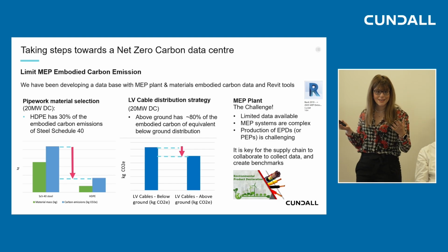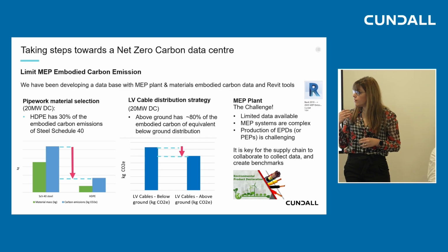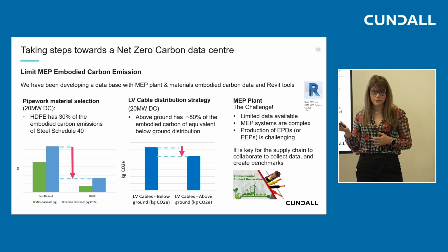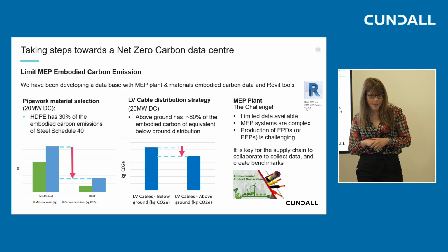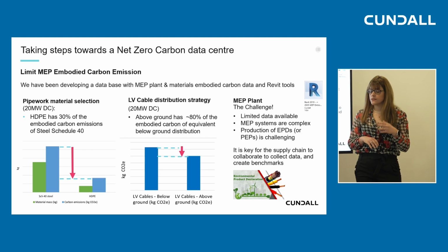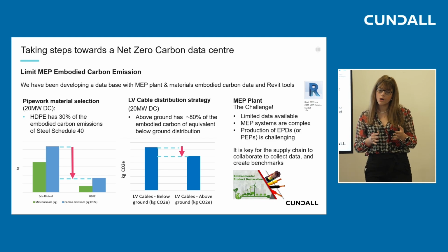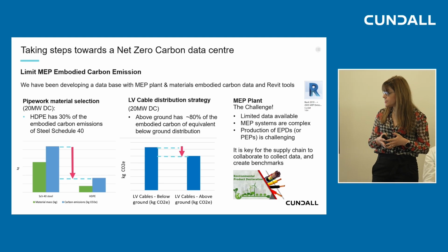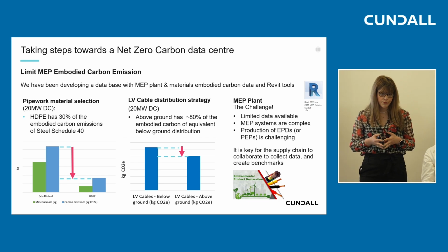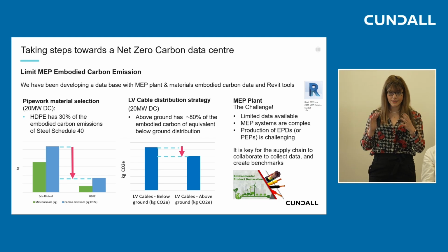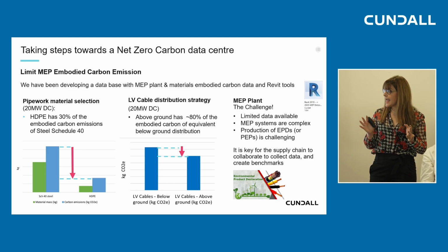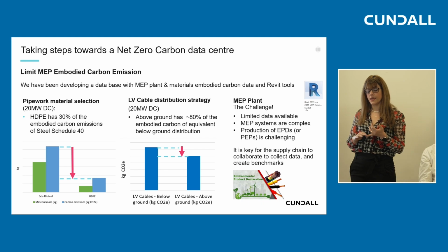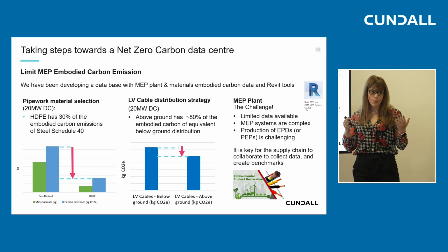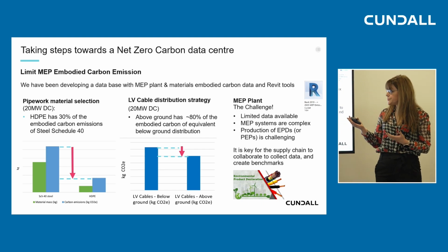Some examples of how we can use the database: pipework material selection. Here we have an example for a 20 megawatt data center, and by looking just at the material of the pipework, going for HDPE pipework will only have 30% of the emissions of steel schedule 40 pipework. This is on the basis of exactly the same pipework diameter and system distribution. Of course the actual numbers will vary depending on the amount of recycling in steel and where it's produced, but you can get the picture.